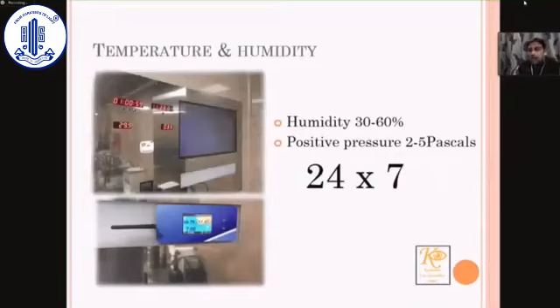During the non-working hours, your OT has to be maintained at a pressure of 2 to 5 pascals with 30 to 60% humidity. The physical parameters can be monitored continuously through an online monitor. If you do not have one, then you have to manually go into the theater and record all these parameters. That's why I told you before, all these electronic gadgets will be very helpful during periods of shutdown, where you can monitor the OT parameters even on your phone from your house.